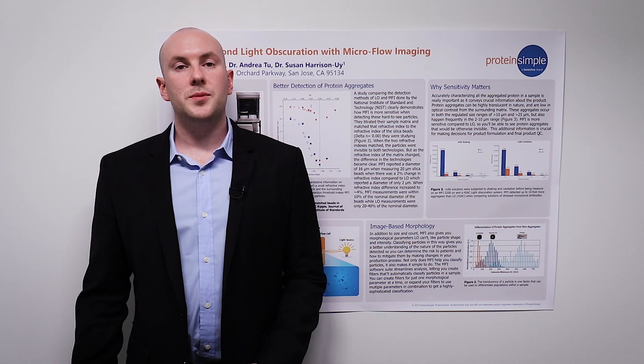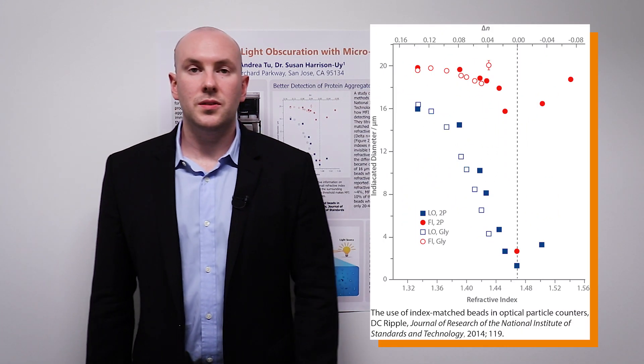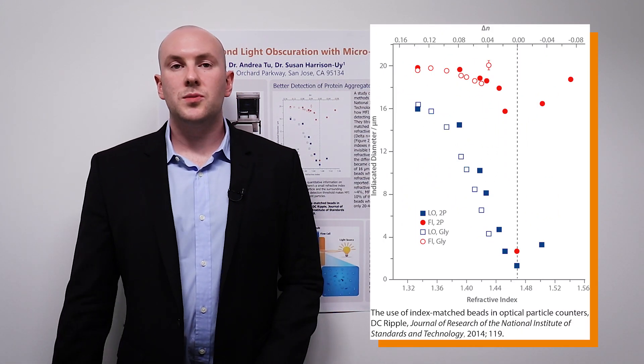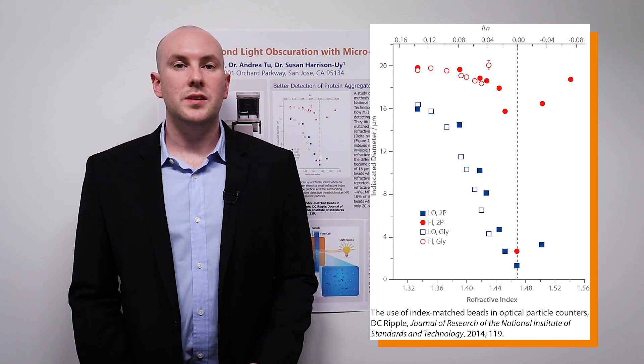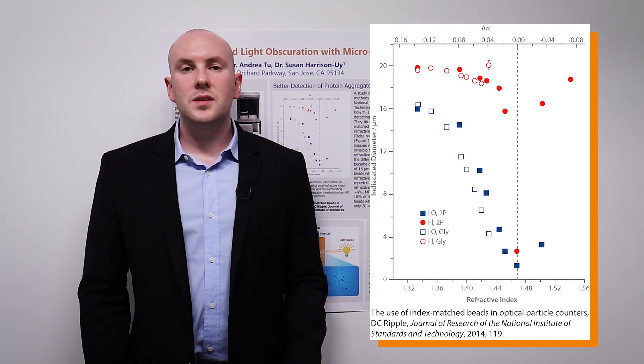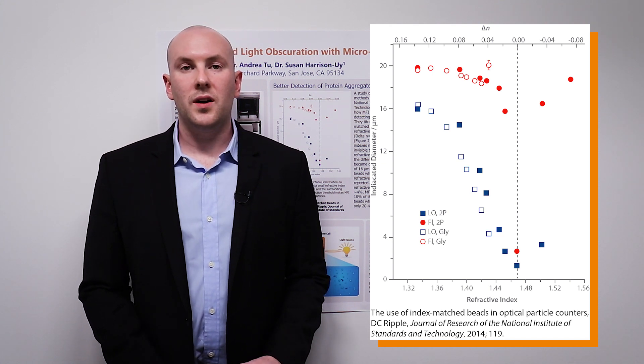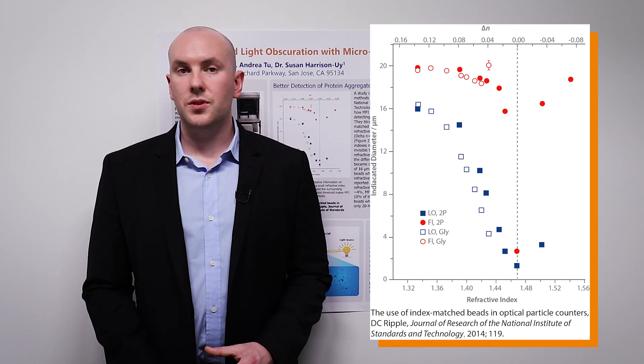One of the main advantages that MFI provides over light obscuration is a more sensitive detection threshold. In a study done by the National Institute of Standards and Technology, polystyrene beads were measured by both MFI and light obscuration in matrices of varying refractive index. The dotted line vertically intersecting the chart represents the point at which the refractive index of the beads and the matrix is perfectly matched — where the beads have become almost optically invisible to both systems.